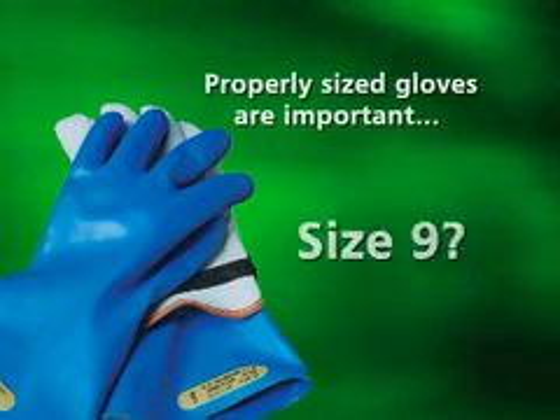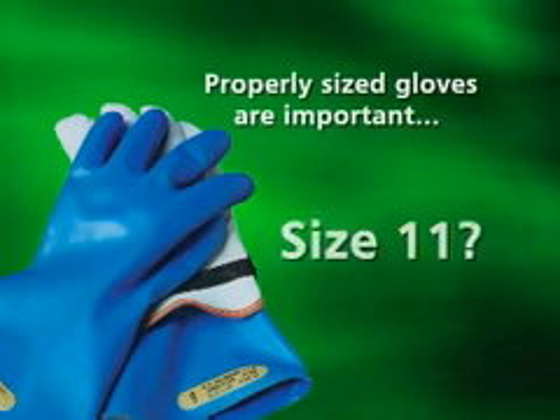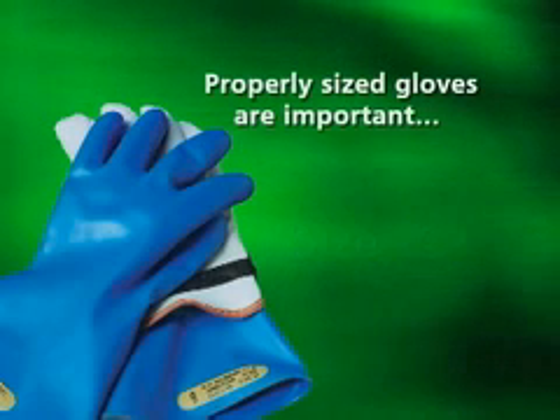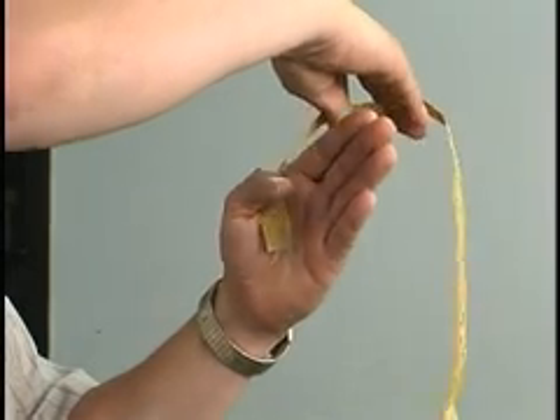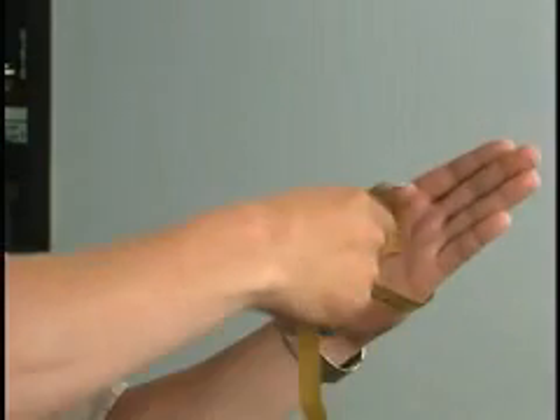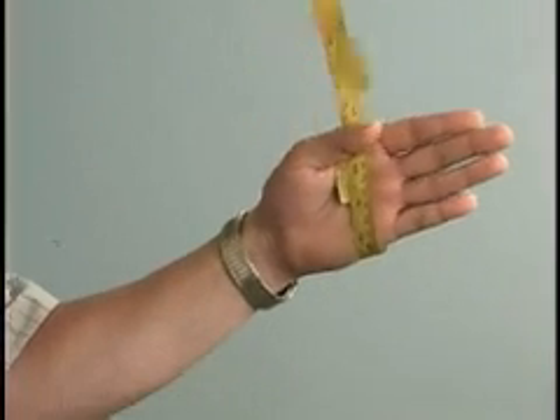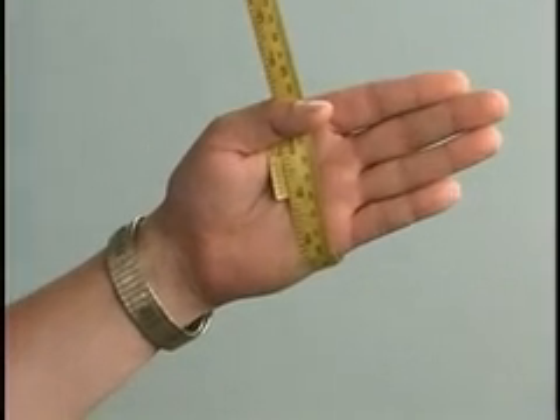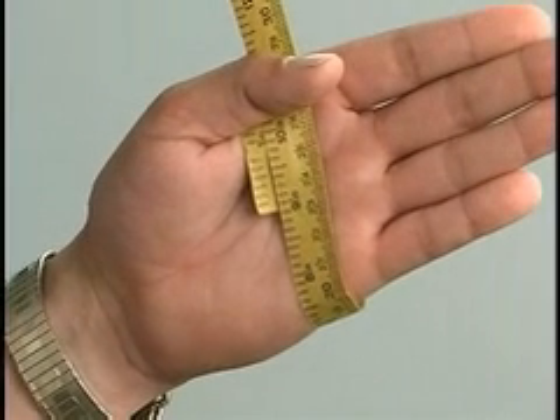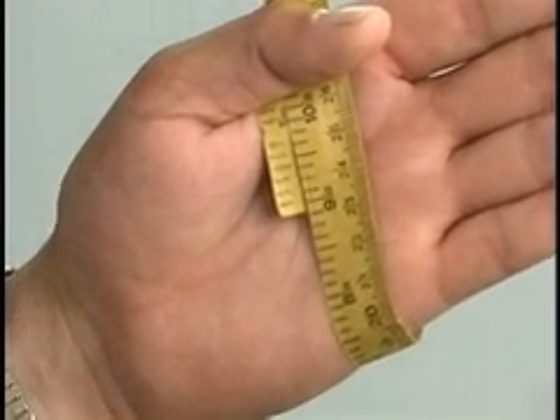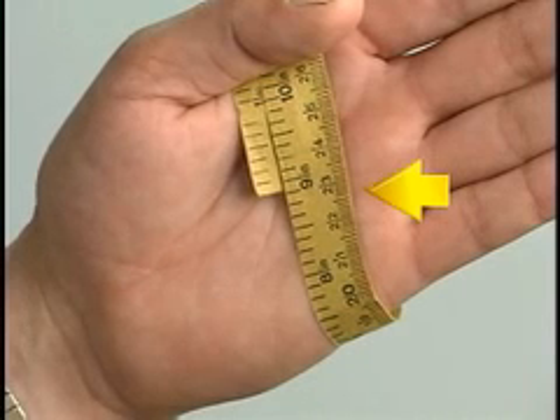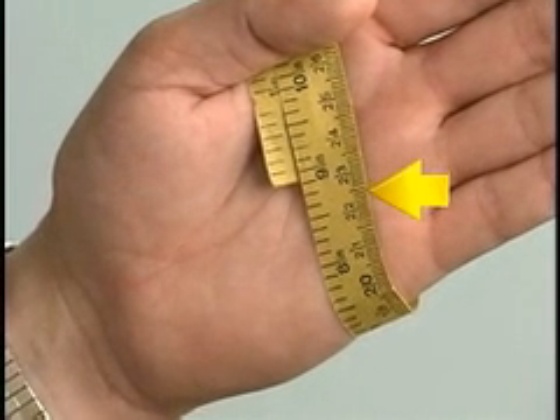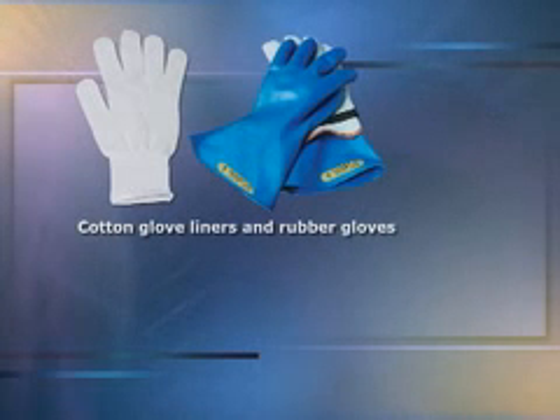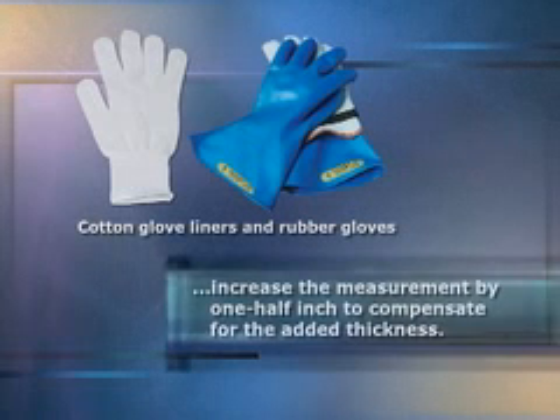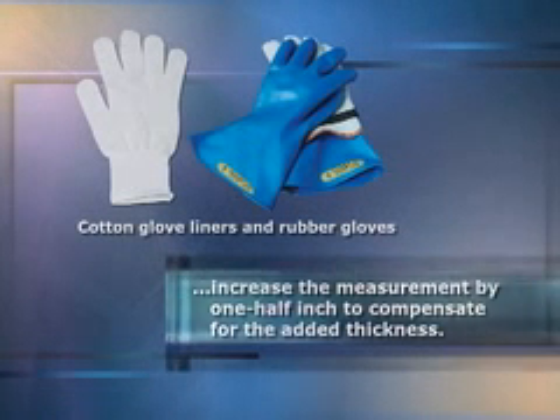Properly sized gloves are important to ensure worker comfort and maximize user dexterity. Measuring the hand is easy, as shown in this demonstration. Using a soft measuring tape, measure around the palm of the hand between the thumb and the index finger. This distance, measured in inches, is the appropriate glove size.